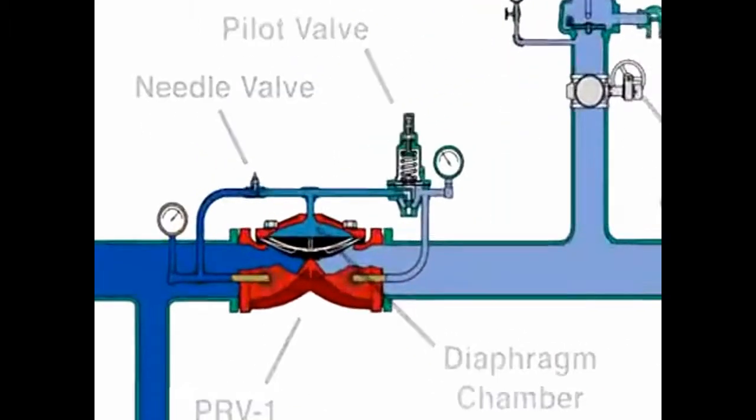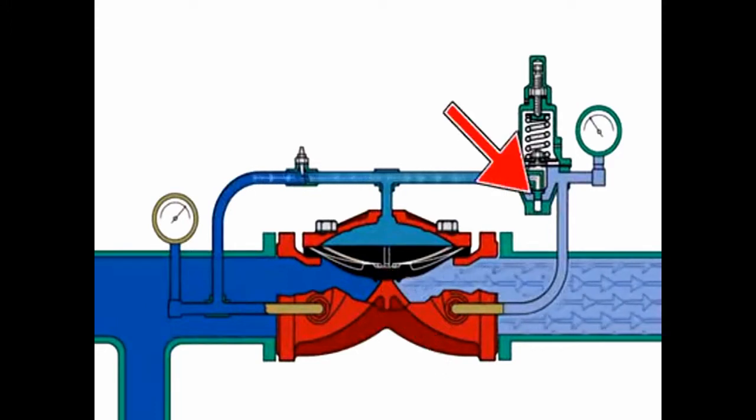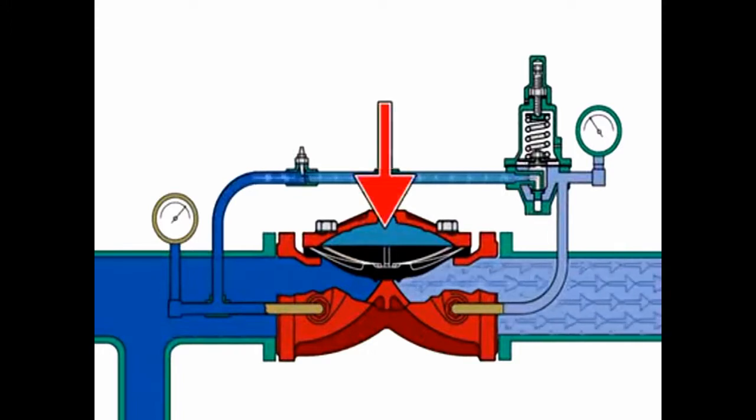When there is no flow demand downstream, the PRV1 seat is closed and the pilot valve seat is closed. With the pilot valve seat closed, pressure is trapped in the diaphragm chamber, which keeps the diaphragm closed on the PRV1 seat.